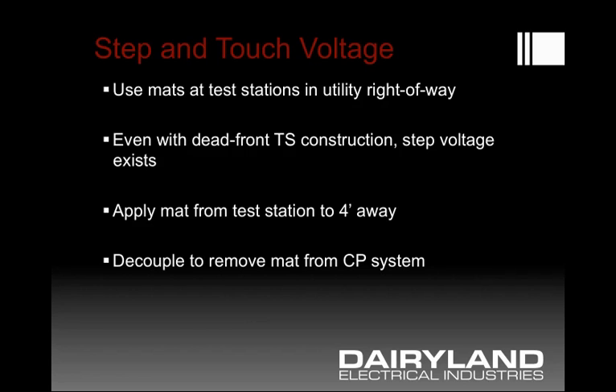The use of grounding mats for step and touch voltage protection is generally done at test stations in a utility right of way. Even with dead-front test station construction, there still is a step voltage in the earth that one can't avoid — one would want to apply the mat within a four-foot distance. Additionally, if it's not a dead-front construction, one could contact the attachment points that reach the pipe and be exposed to touch voltage as well.